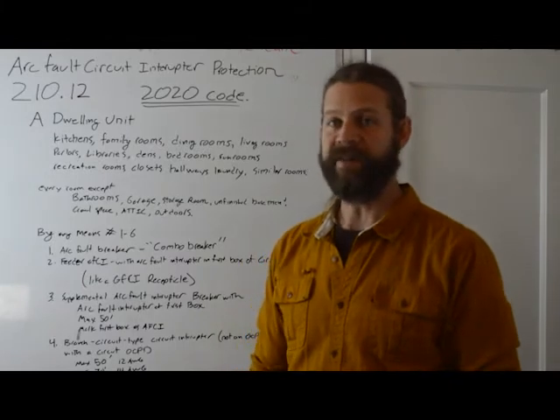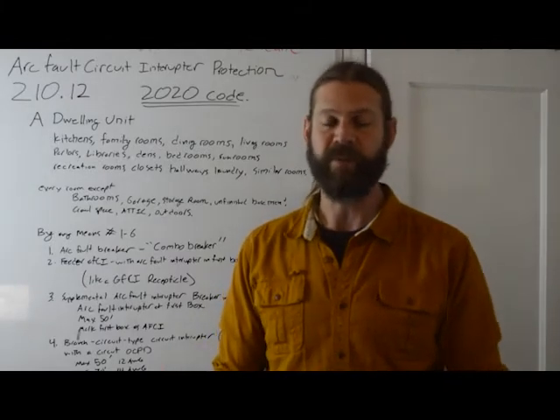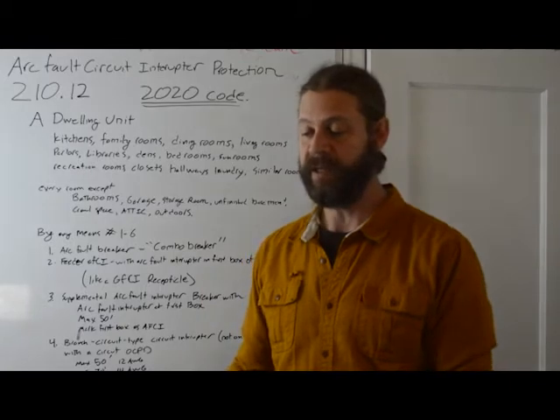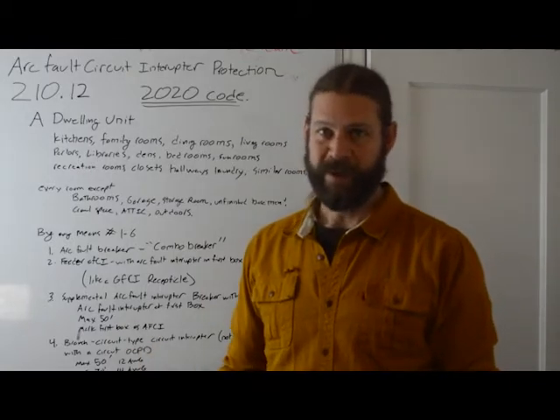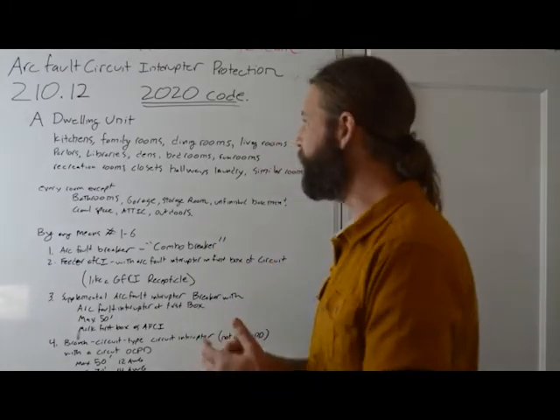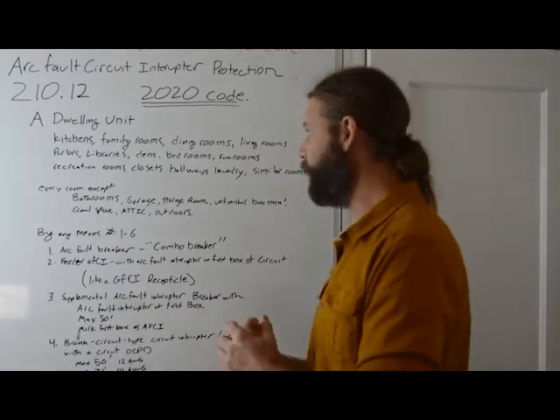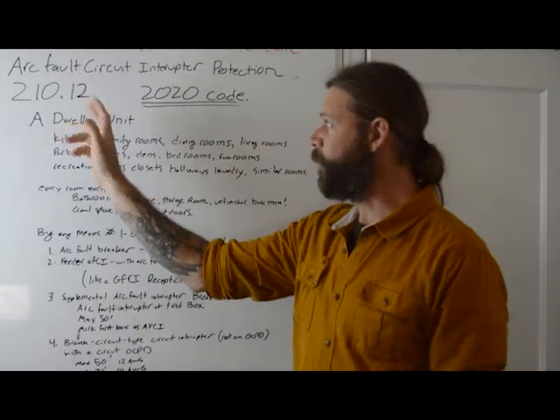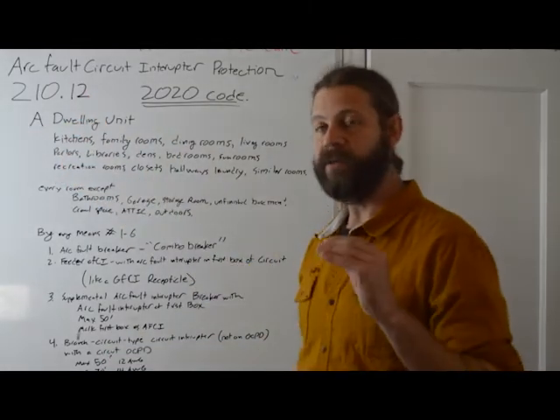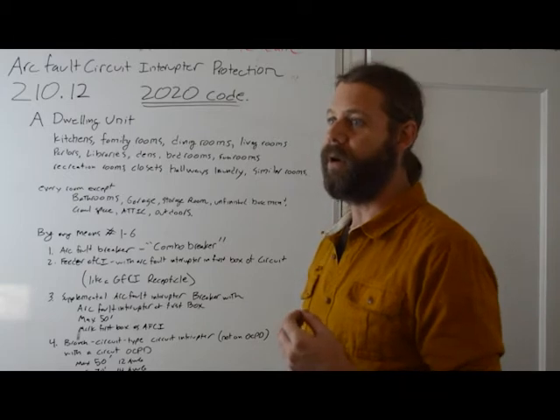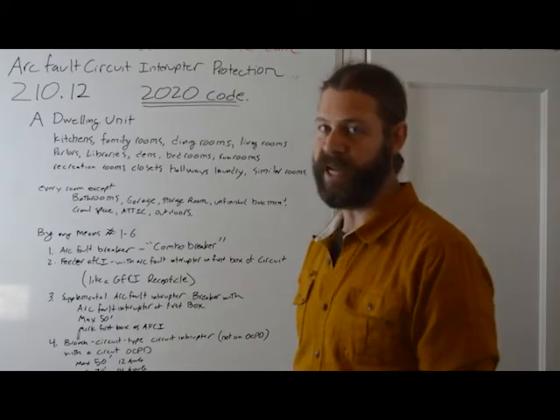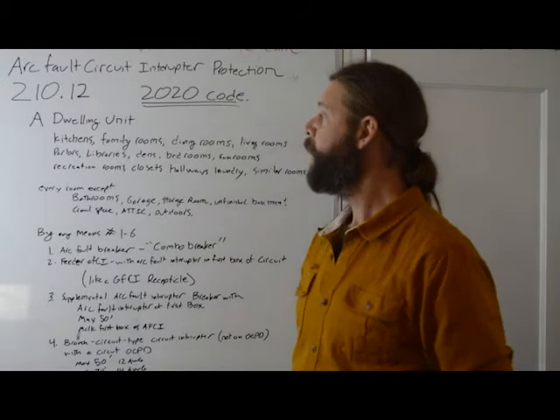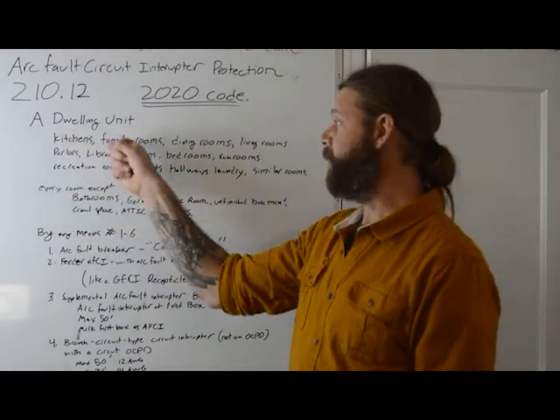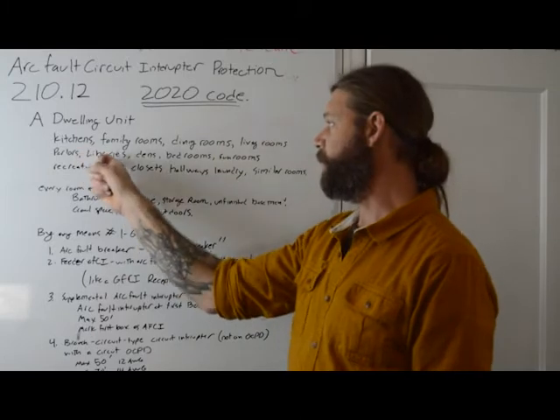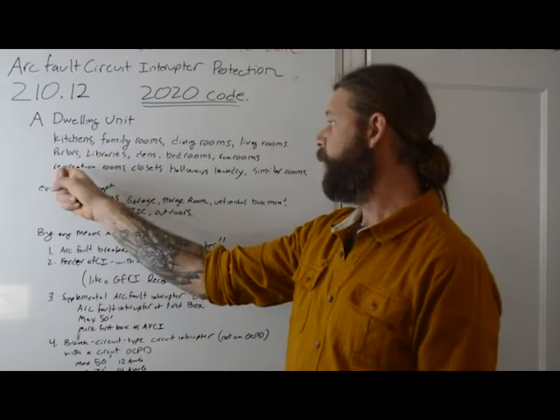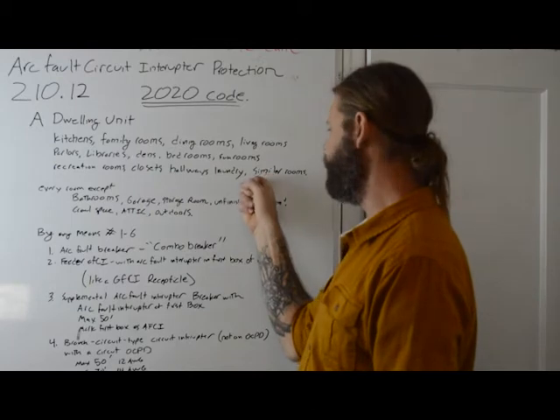And so in about 2005, they started requiring arc fault breakers to protect houses. And they initially had them in like bedrooms. But we've added them to a whole bunch of rooms, so we're going to go through the list real slow. So 210.12(A), dwelling units. Arc fault interrupters are associated with dwelling units. They are for the protection of people against fire. So, they are required in kitchens, family rooms, dining rooms, living rooms, parlors, libraries, dens, bedrooms, sunrooms, recreation rooms, closets, hallways, laundry, and similar rooms.